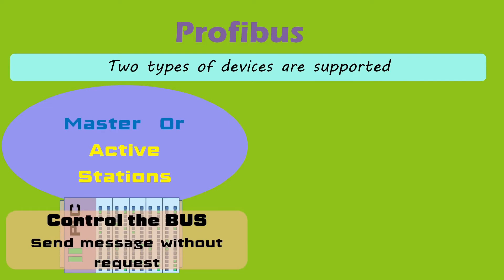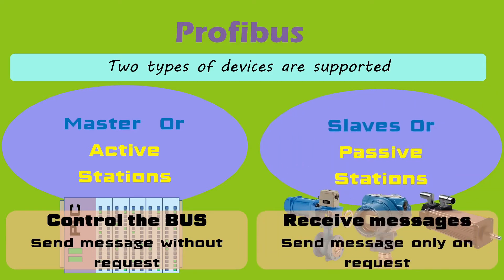Profibus supports two types of devices — Master and Slave. Master devices control the bus; when they get the right to access the bus, they can transfer messages without any remote request. These are also referred to as active stations, and a PLC is an example of a master. Slave devices are normally input devices like input blocks, transmitters, sensors, and actuators. They can receive messages from the master and, on request from the master, can transmit messages back. They are also referred to as passive stations.